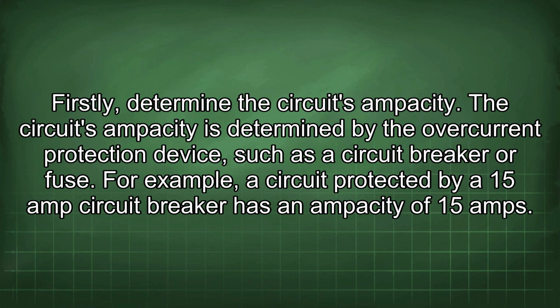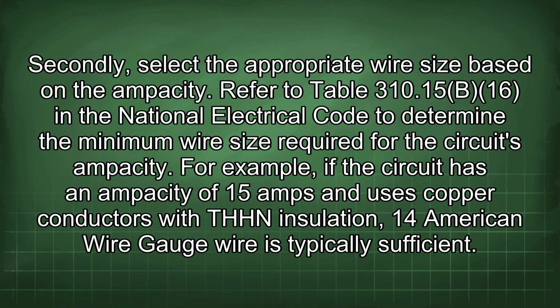The circuit's ampacity is determined by the overcurrent protection device, such as a circuit breaker or fuse. For example, a circuit protected by a 15 amp circuit breaker has an ampacity of 15 amps. Secondly, select the appropriate wire size based on the ampacity. Refer to Table 310.15(B)(16) in the National Electrical Code to determine the minimum wire size required for the circuit's ampacity. For example, if the circuit has an ampacity of 15 amps and uses copper conductors with THHN insulation, 14 American wire gauge wire is typically sufficient.